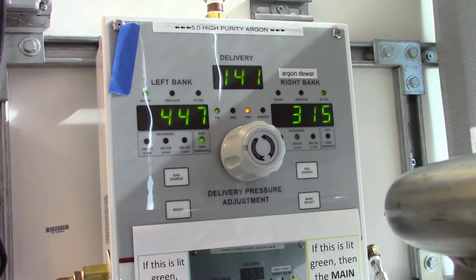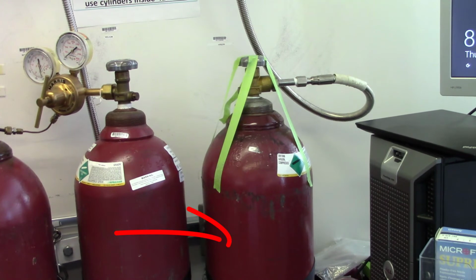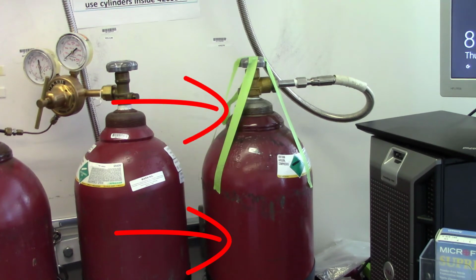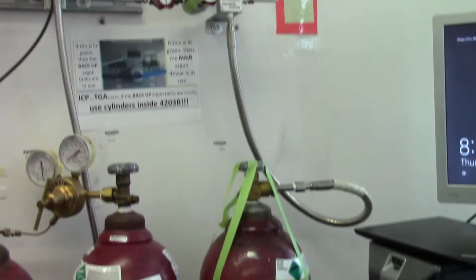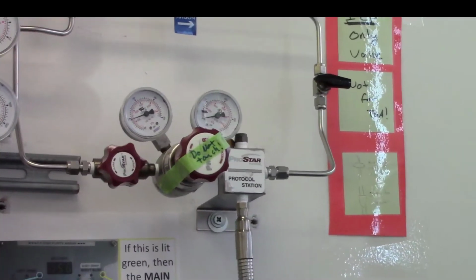In this example, you see that the argon dewar is in use, so it's okay to set up the ICP to run your samples. Next to the ICP, there is a backup cylinder that has been taped off to remind you that it's very rarely needed. The regulator attached allows the flow of argon from either the dewar in the other room or the cylinder. Since you will almost always be using the dewar, you will want to leave the taped cylinder alone.